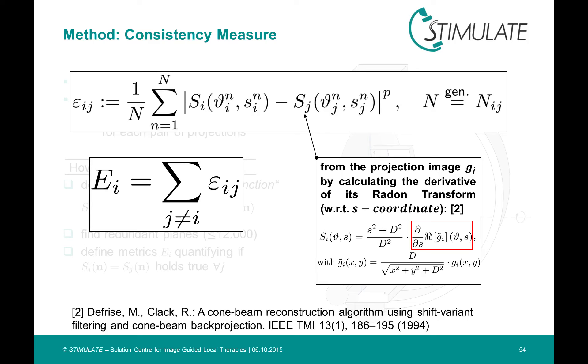You can see in the formula on the right, that you basically have to calculate the 2D radon transform of the projection images, denoted with R. And afterwards, you just have to differentiate it and do some weighting. We can do this as a preprocessing step, by an appropriate sampling of the intermediate function.